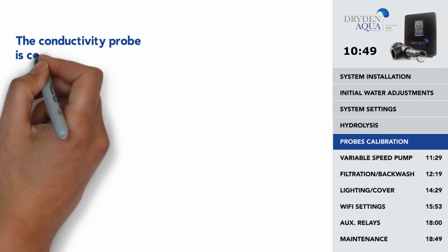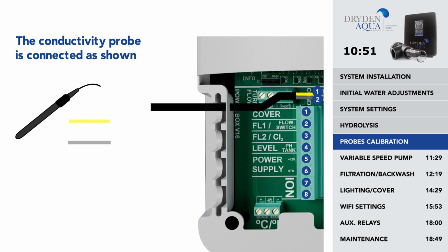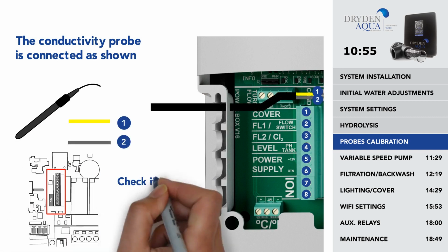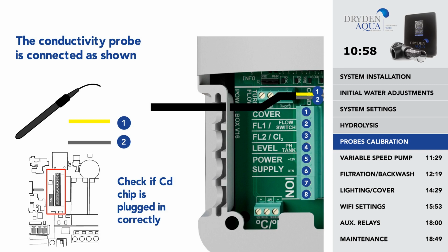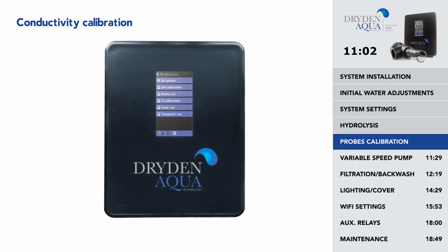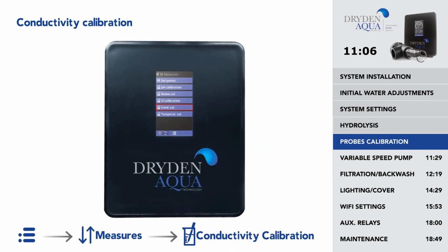First, connect conductivity probe as shown. Check if the chip is plugged in correctly and make sure the green LED is blinking. Then, go to the Measures menu and press on Conductivity Calibration. It is recommended to calibrate the conductivity probe once a month during the usage season.